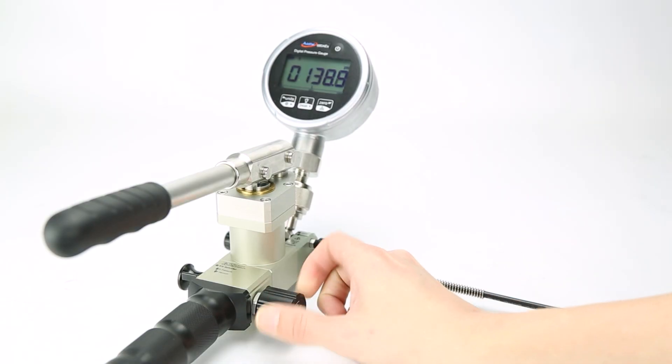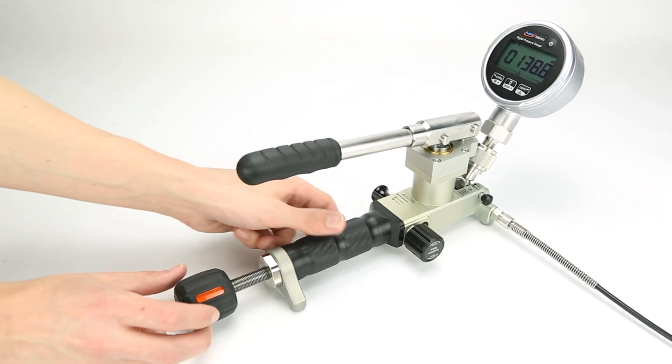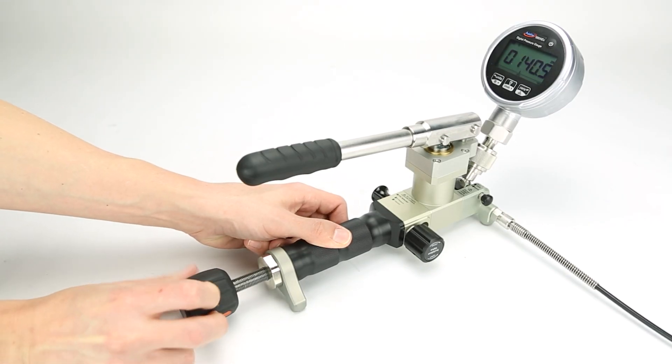After nearing the desired pressure, close the isolation valve, then use the fine adjust knob to dial in the correct set point according to the reference device.